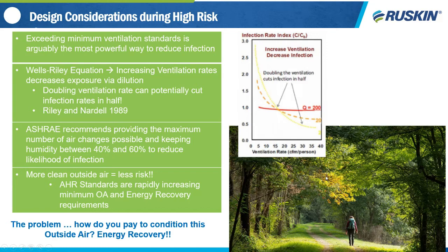Glenn's phrase hit it right on the head: dilution is the solution to pollution. The bottom line up front, exceeding minimum ventilation standards is arguably the most powerful way to reduce infection. I have a graph on the right here from the Wells-Riley equation. The Wells-Riley equation states that increasing ventilation rates decreases exposure via dilution. In fact, doubling your ventilation rate can potentially cut infection rates in half.